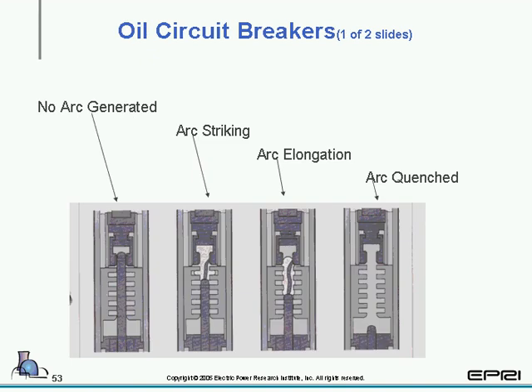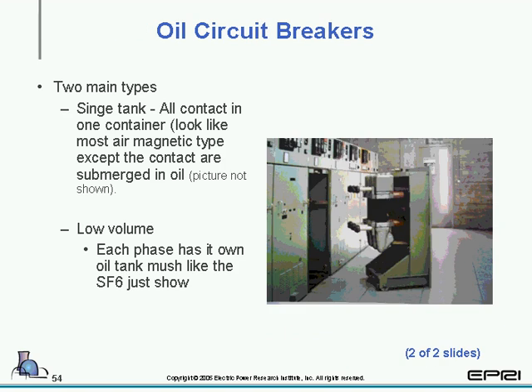Oil circuit breakers basically work identical to what we've just talked about, except that in the oil circuit breakers, over the SF6 gas, oil is used to extinguish the arc. There's pluses and minuses to each design. Oil circuit breakers have two different types, unlike the SF6. The first design is a single tank, where all three phases of the contacts are submerged in one single tank. That picture is not shown.